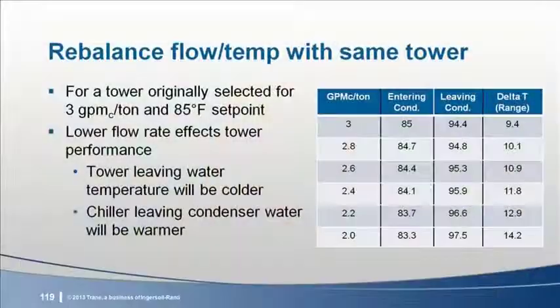To rebalance an existing tower with a chiller at a lower flow rate but at the same load, it leads to something like this chart. For a tower originally selected for 3 GPM per ton and 85-degree leaving water temperature, dropping to 2 GPM per ton gives us 97.5 degree water entering the tower instead of 94.5 and 83.3 degree water leaving the tower, increasing its delta T or range by nearly 5 degrees.